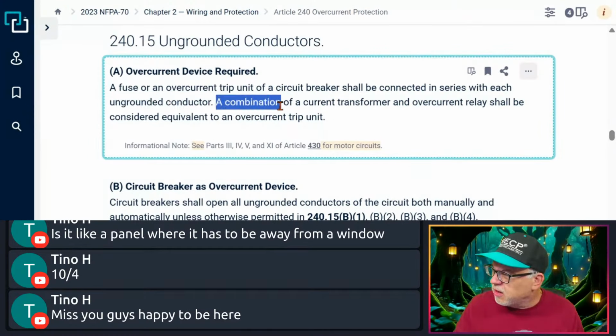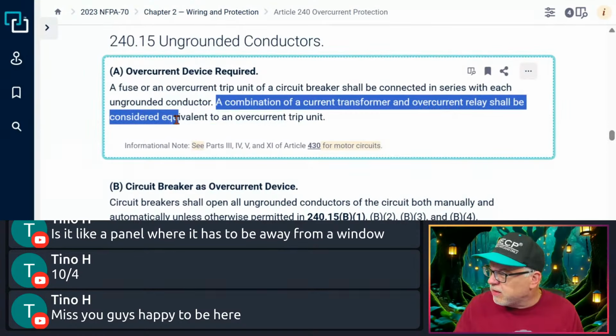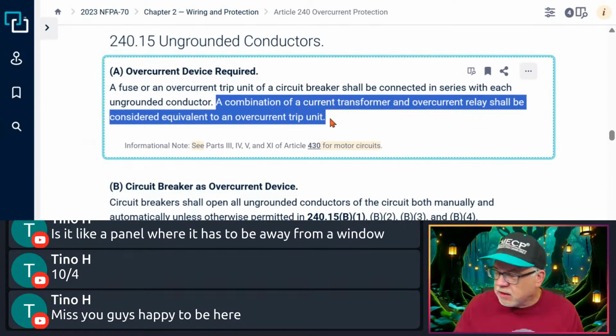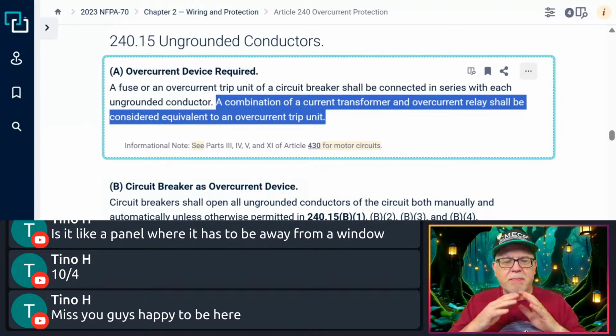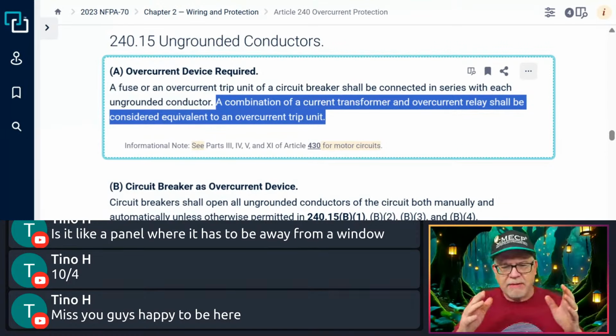A combination of a current transformer and overcurrent relays shall be considered equivalent to an overcurrent trip unit. Okay, so depending on the different type of equipment you have, you may have a current transformer and an overcurrent relay. I think we had a question about that the other day. Is a relay considered the same as overcurrent? If it's an overcurrent relay in combination with a current transformer, then that can be considered an overcurrent trip unit together, or considered equivalent. But that's all based on the makeup of the system, and you're usually buying something that way. You're not making these separately from different components.